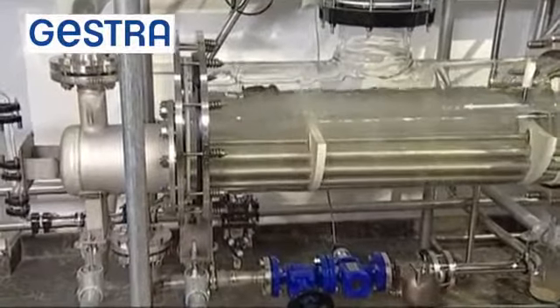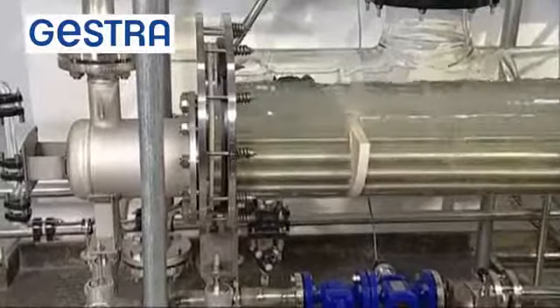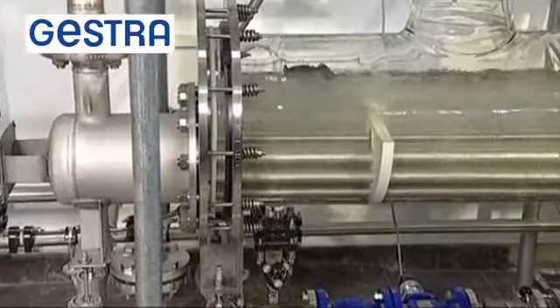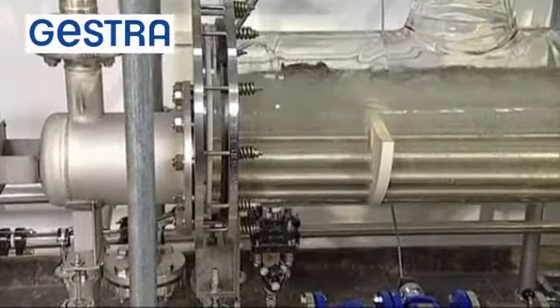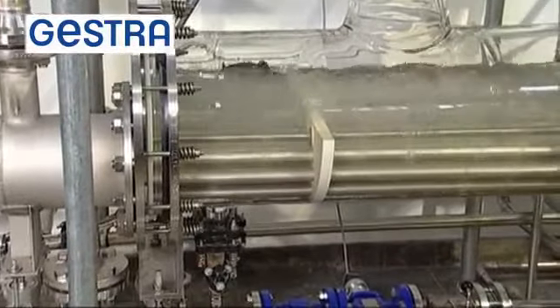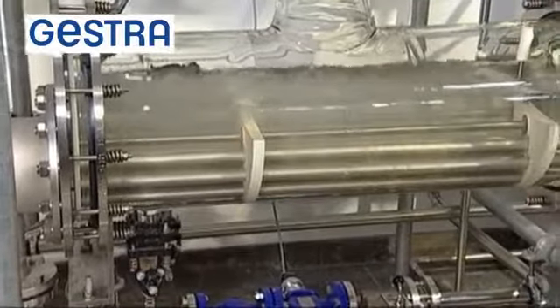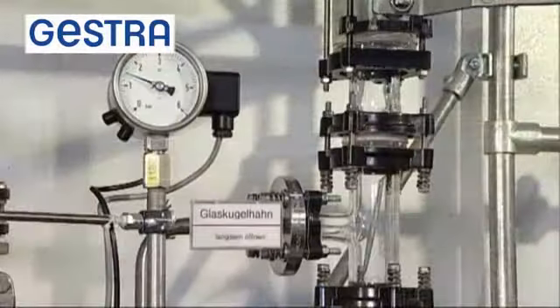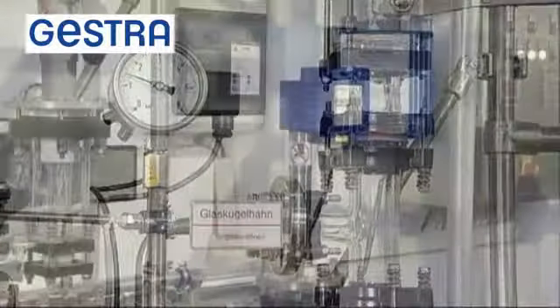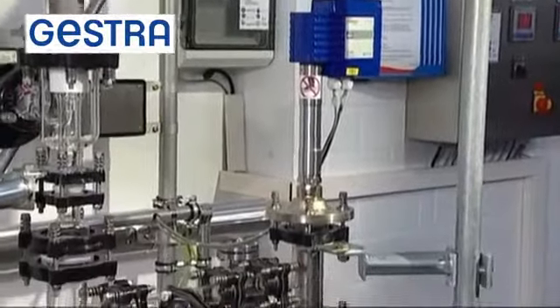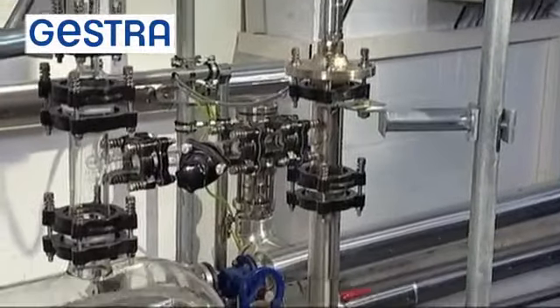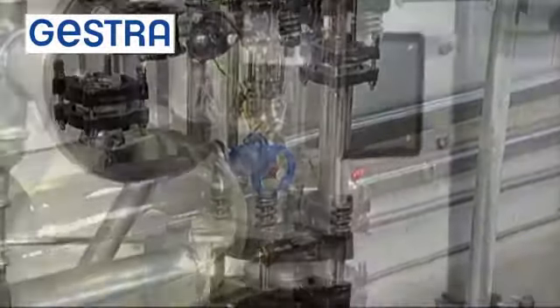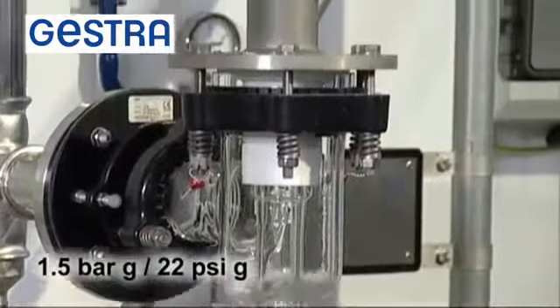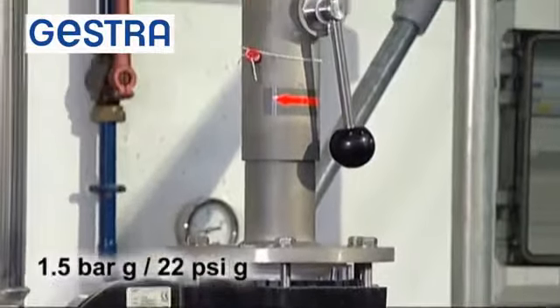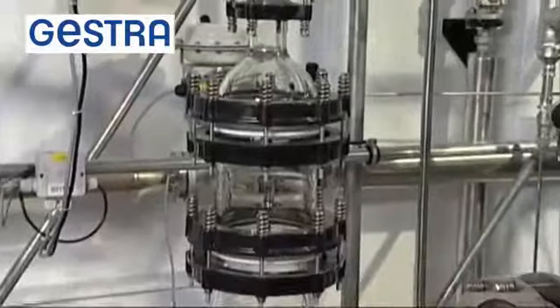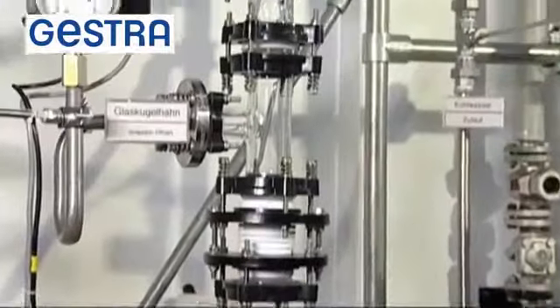The steam generator consists of the following components: the horizontal evaporator with a stainless steel head for the primary steam inlet and condensate outlet, as well as 16 evaporator tubes, a pressure gauge with pressure transducer and a level measurement unit employing the capacitive measurement principle in an external measuring pot, a safety valve with a blow-off pressure at 1.5 bar gauge, and a steam outlet with a ball valve made of glass.